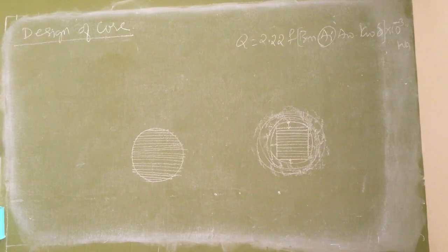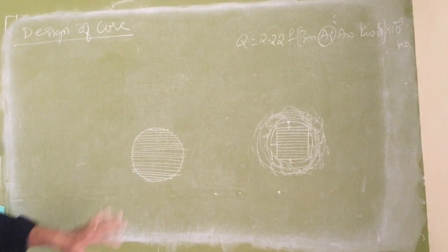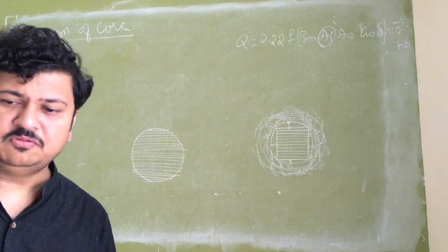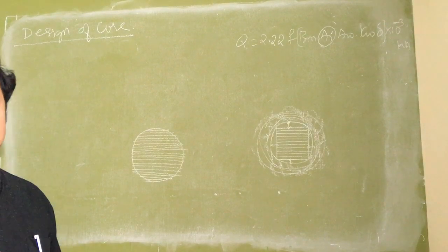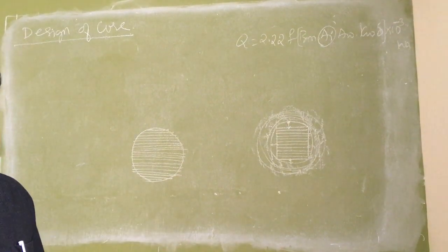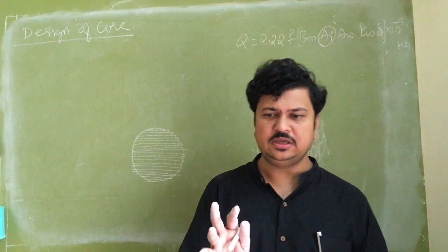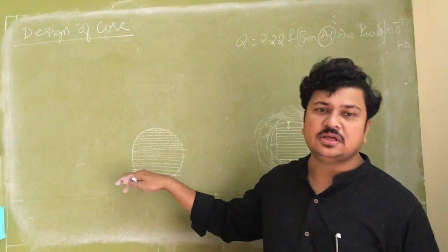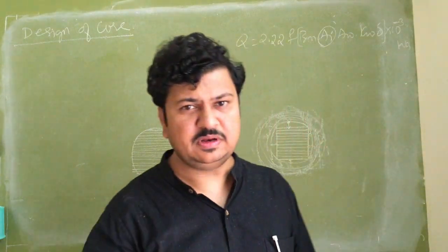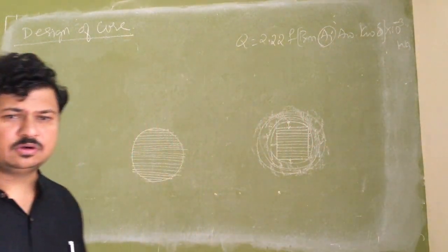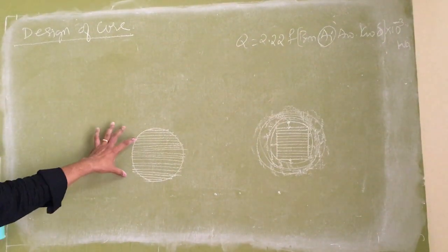That is the biggest disadvantage. I have to fabricate laminations of various widths, and if the transformer size changes, the lamination size changes. So it is extremely difficult to achieve, one thing. Second, it is very costly, because labor work and material wastage will be more, therefore the cost of the core will be more. So the economy gets hampered here.